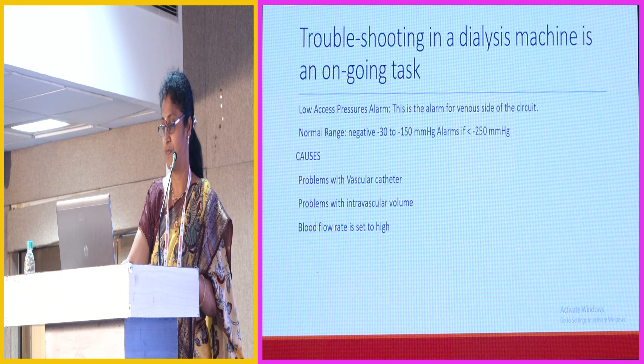So these are the basic pressures that we see in the CRRT machine, the basic alarms. And how do we go about troubleshooting? Once you understand the basic physiology, you can go for clear troubleshooting. The low access pressure alarm comes when it is less than minus 250. The problem can be with the vascular catheter, so check the catheter issues. Try to pull out the catheter a little bit, rotate it, check the flows, because if the catheter tip is abutting the wall, you will have very low venous pressures.